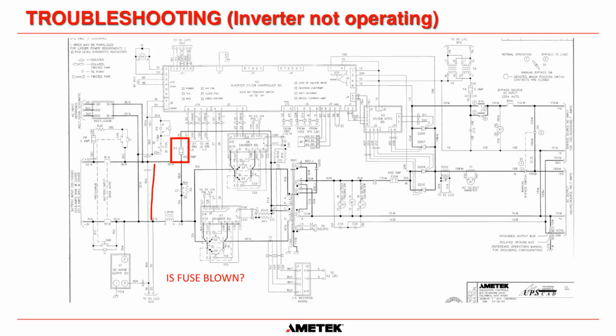we said between here and here we should have greater than 105 volts DC, which means we have to have at the center tap of the transformer greater than 105 volts DC. And if the fuse is blown and we're not getting DC down to this point here, then the inverter will never ever start. So how do you check a fuse? A lot of people get confused about this sometimes, okay?